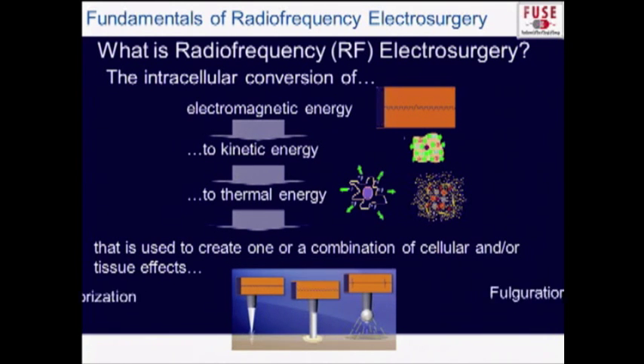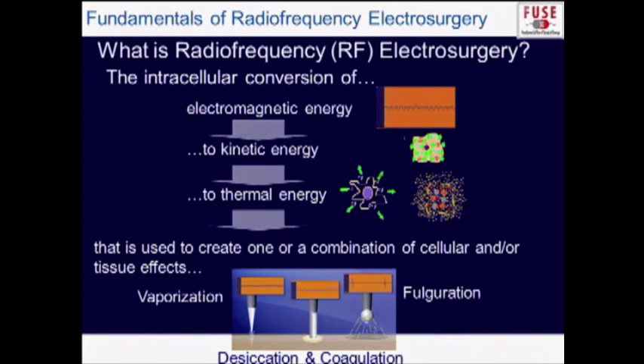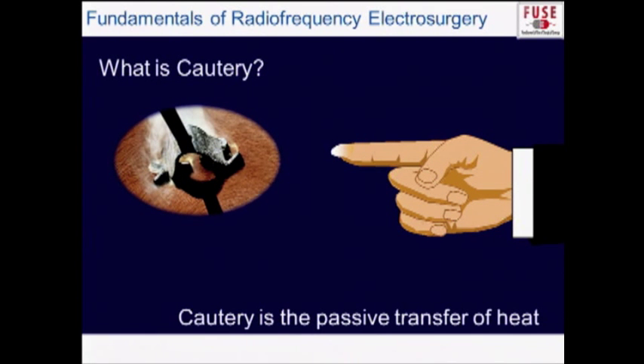RF electrosurgery is the intracellular conversion of electromagnetic energy to kinetic energy to thermal energy — two conversions occur. That thermal effect can then manifest in tissue to either vaporize it, coagulate it, or fulgurate it. It is not cautery. Cautery is the passive transfer of heat — like lighting a match or branding a bull. With radiofrequency electricity, we are actually heating the tissue, which then heats the instrument.